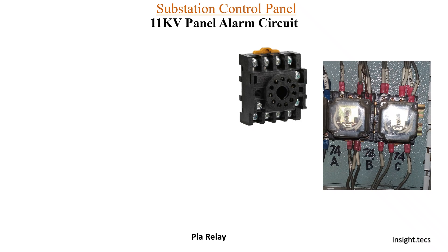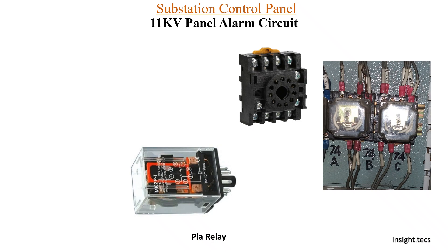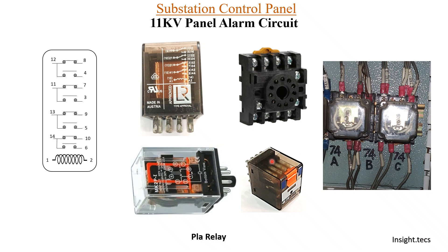So PLAR relay — PLA is the make of this relay. This is somewhat what it looks like. This is the base of this relay; we have to fix this on the panel. And this is the actual relay, which gets fixed inside the base. Nowadays we also have this kind of PLAR relay, and in some panels this kind of micro relay. Basically, inside the PLAR relay we have an operating coil and we have a few NO and NC contacts. This is the operating coil, this is the NC contact, and this is the NO contact. Whenever the coil gets operated, the NO gets converted to NC and the NC gets converted to NO.